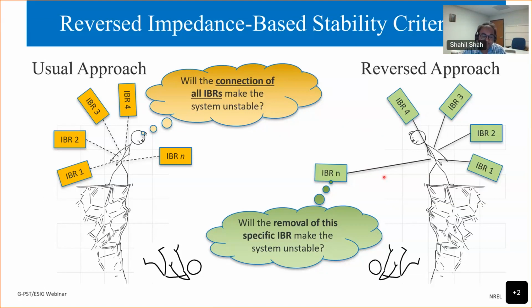This is also a more practical way of looking at stability, because whenever we see oscillations or stability issues, a system planner doesn't want to understand how each IBR in the system is impacting the oscillation modes or stability. We select a few IBRs depending on their size, and their importance in terms of other stability aspects like frequency stability or voltage stability, and how much fault current they contribute. So a system planner wants to know only about a few IBRs, like how they impact the system modes.